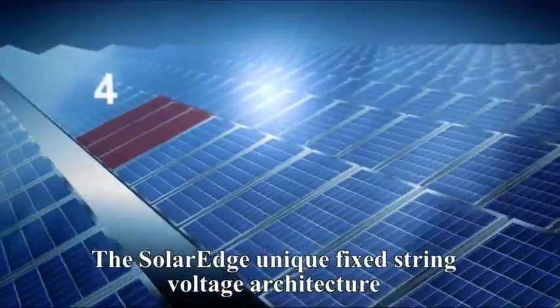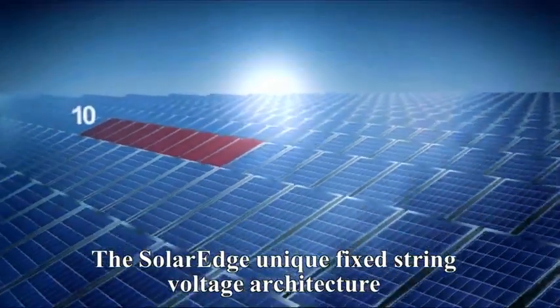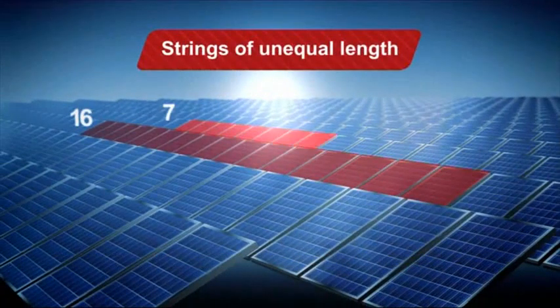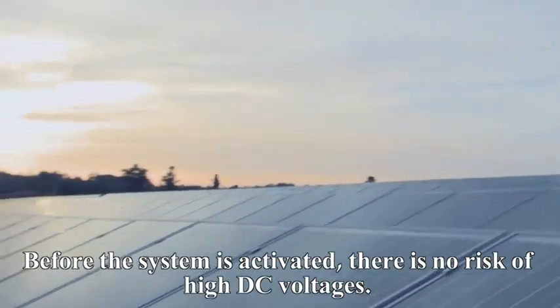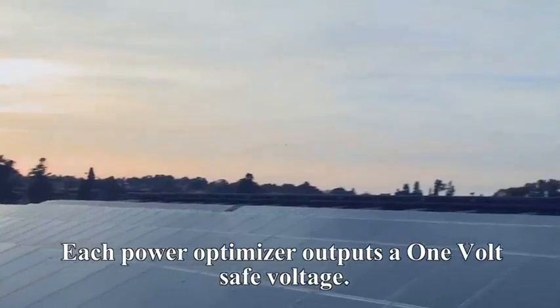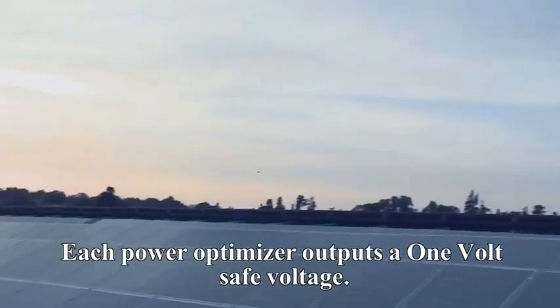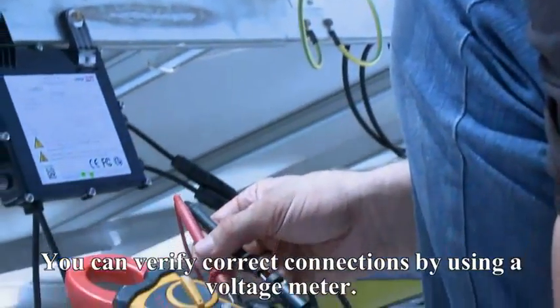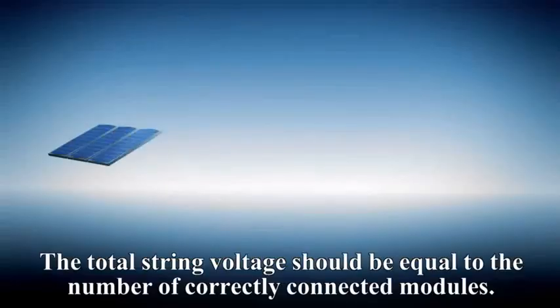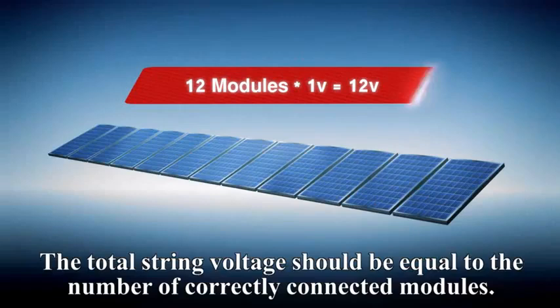The SolarEdge unique fixed string voltage architecture allows you to connect strings of unequal length in parallel. Before the system is activated, there is no risk of high DC voltages — each power optimizer outputs a one-volt safe voltage. You can verify correct connections by using a voltage meter; the total string voltage should be equal to the number of correctly connected modules.